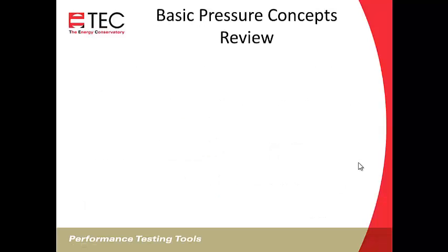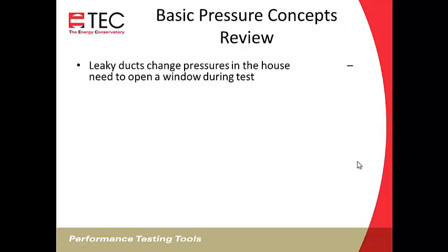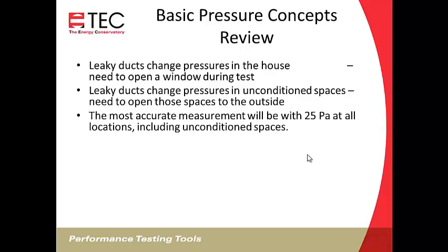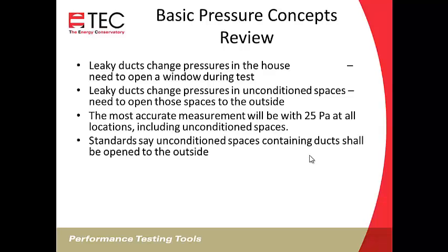So review of those basic pressure concepts. Leaky ducts change pressures in the house. So we need to open a window during our test to get accurate results. Leaky ducts change pressures in unconditioned spaces, so those unconditioned spaces need to be open to the outside. Our most accurate results are going to be when we have 25 pascals between the duct and all of those unconditioned spaces.